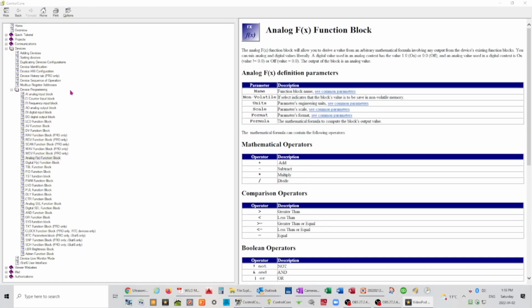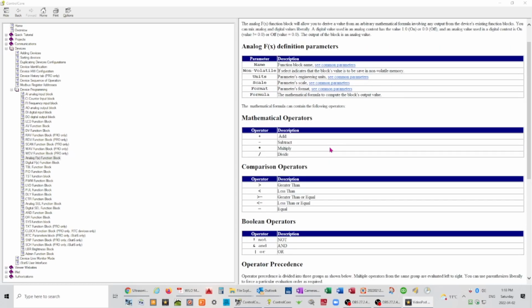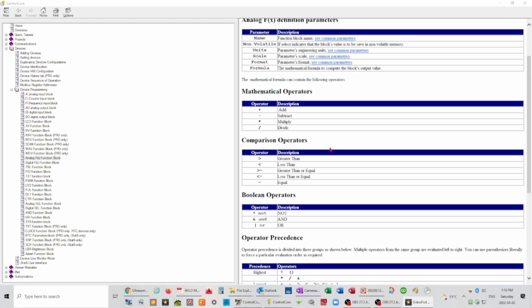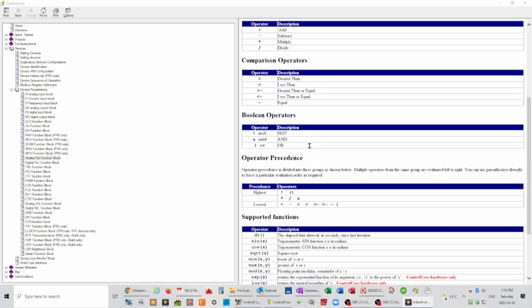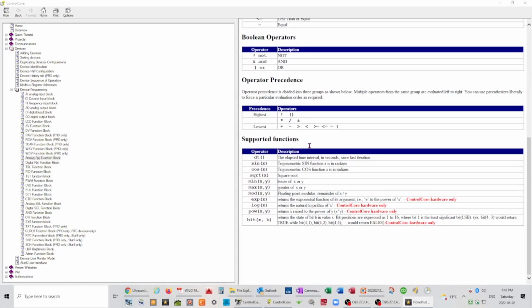One of the most important blocks is the analog function block, and this is basically where you create your formulas. So you create your target temperature formula based on outdoor temperatures, and I'll show you that in a bit. And these are the operators that you can use. So you can plus, minus, multiply, divide, greater than, all that kind of stuff, not, and, or, and then highest and lowest, that kind of thing. And then you've got some higher function operators that you can use as well. And these do take some time to figure out. You might be able to do something in another program that you then have to convert to using just these available functions in this program. So I had to do that with something using log, and it took me a while to figure out the right call on how to convert everything to using log.